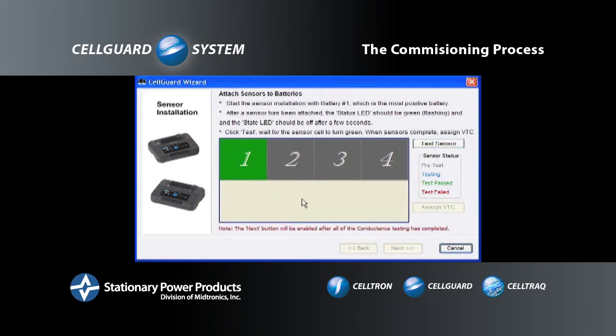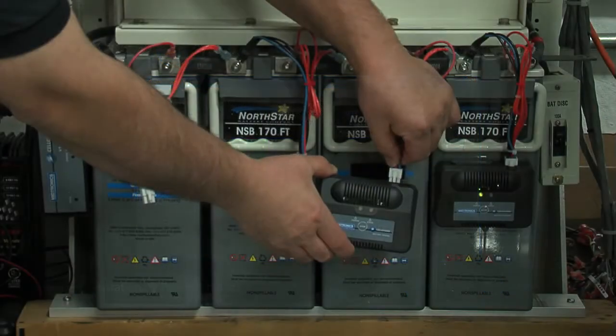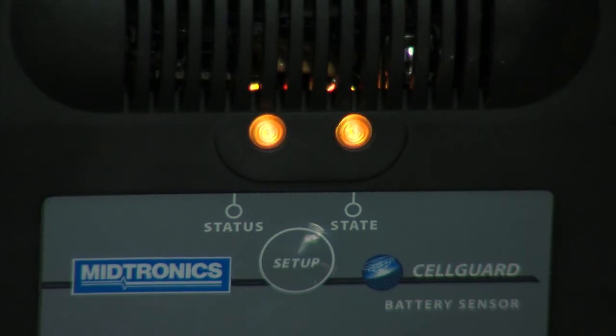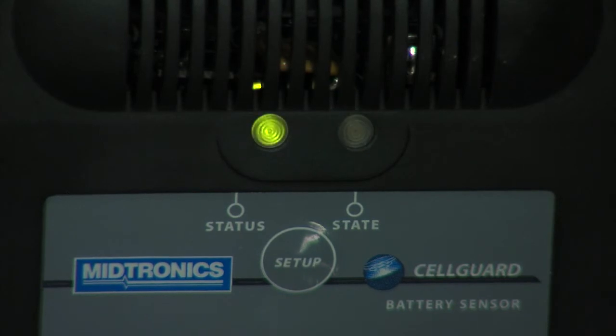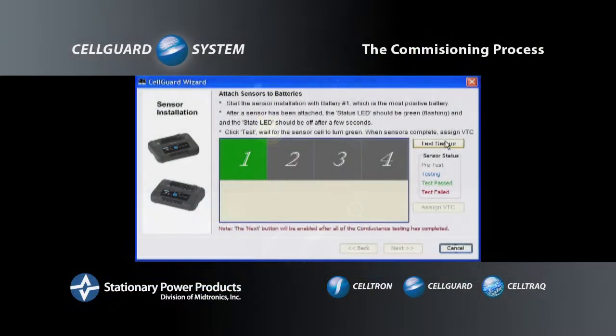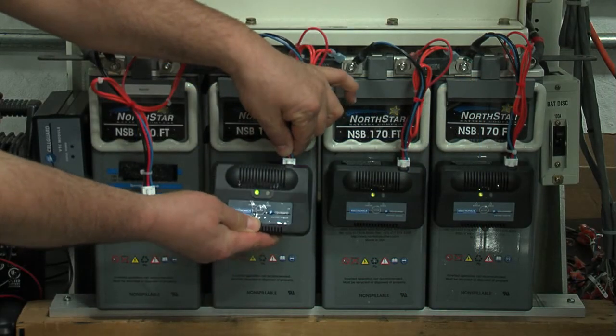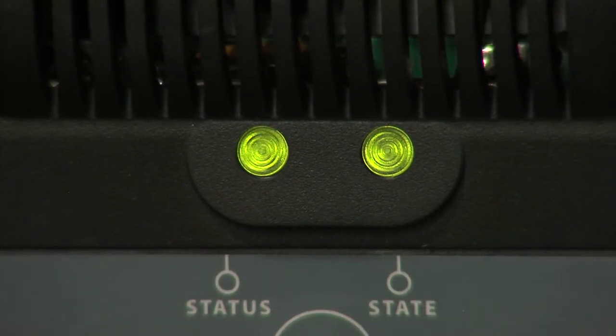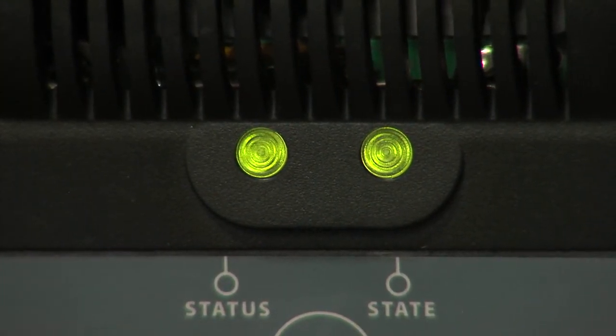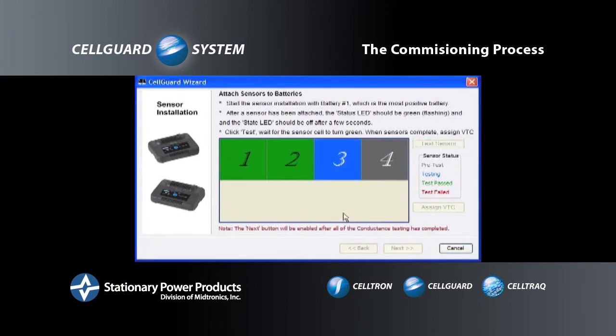Now that the square has turned green, connect the next sensor to battery 2. The LEDs for sensor 2 will go through their power-up sequence. Wait until the status LED is in the continuous flashing green state, and then click Test Sensor. The square for sensor 2 will turn blue. Wait for the square for sensor 2 to turn green, and then connect the sensor for battery 3. Wait for the LEDs to go through their power-up sequence, and click Test Sensor. Again, the square turns blue.